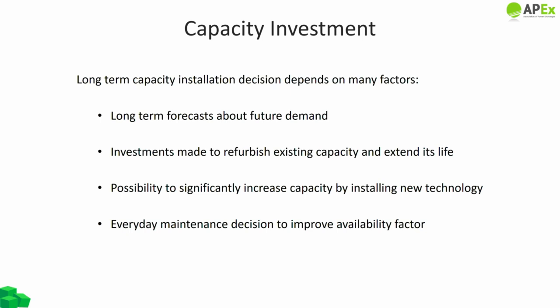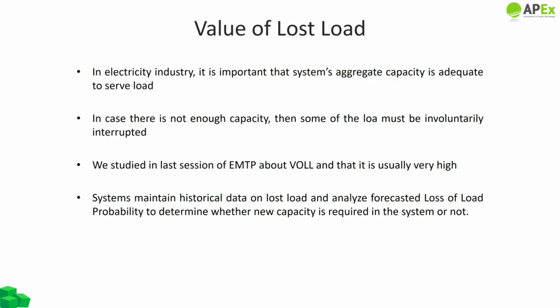Other capacity decisions are shorter term: investments can be made to refurbish existing capacity and extend its useful life, or to significantly increase the capacity of an existing plant by installing new technology. Everyday maintenance decisions are also capacity decisions — a well-maintained plant is less likely to have unplanned outages, giving it a much higher availability factor. If a system has excess capacity, it may make economic sense to mothball or retire some capacity. It is important to ensure the system's aggregate capacity is always adequate to serve the load, accounting for unplanned outages and uncertainty about load growth.